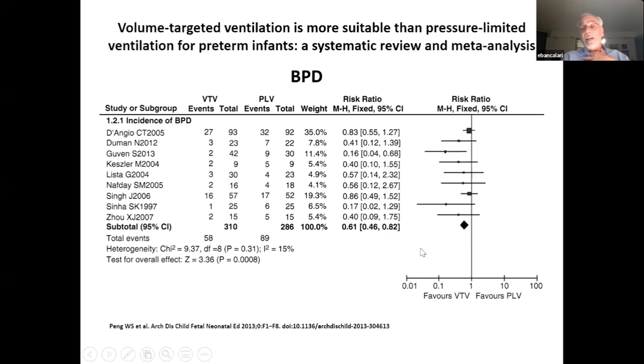The reason why we are not willing to start using volume-targeted ventilation in all patients is because there are issues with it. It's a technique that requires the proper equipment, and there are a number of things that can make the detection of tidal volumes inaccurate: flow sensor failures, leaks around the endotracheal tube, and this will obviously limit the efficacy or maybe increase the risk of volume-targeted ventilation if the signal is not accurate. The other thing is that frequently people set the pressure limit at a level that is too low, and then the ventilator cannot generate the pressure necessary to deliver a normal tidal volume. And for us, the most difficult limitation is that it's very difficult to know exactly what the ideal tidal volume is that a patient needs at a certain point during their evolution.